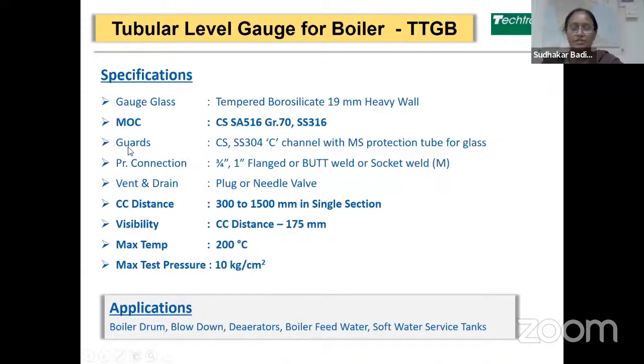So these are the specifications. This is available in materials of CS SA516 grade 70 and SS316. Then the CC distances are available from 300 to 1500 mm in single section. And for this, the visibility you will get is CC distance minus 175 mm. It is suitable for a maximum temperature of 200 degrees Celsius and a test pressure of 10 kg per centimeter square. It can be used for boiler drums, blowdown tanks, deaerators, boiler feed water, and soft water service tanks in boiler applications.